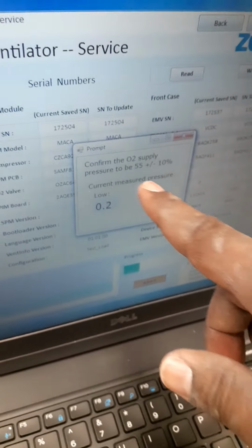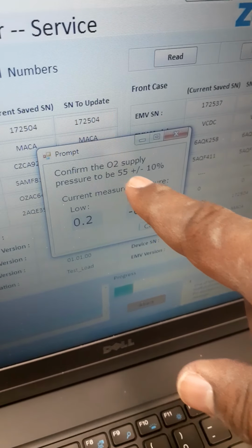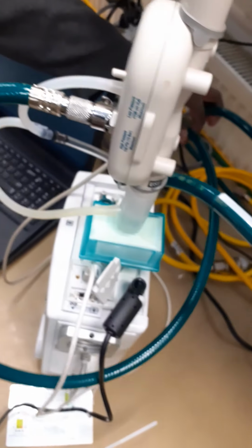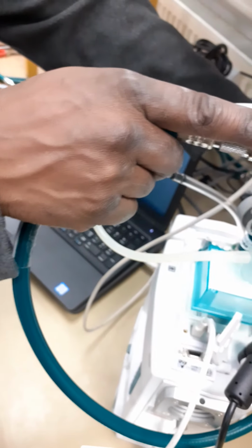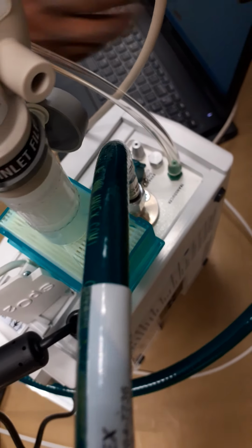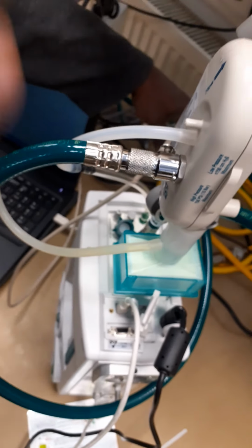Okay, this is when we get into the pressure. So we're dealing with high pressure O2 supply. It's asking me to enter 55 PSI. So as you see, we already have this connected. The RCS kit comes with this Y connector so that you can have one of the hoses going straight into the meter and the other hose going straight into the device itself. That way you're getting an accurate reading of what's coming into this whole device. All right, remember this is a meter. So it wants 55 PSI.